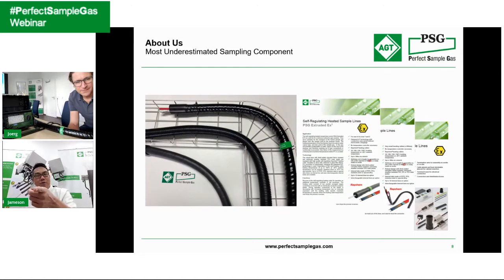The PowerPoint slides show three different bending radii for the heated line. The one on the extreme right, bending the most, will catch many people by surprise - how can a heated line bend up to 90 degrees on a cable tray? Usually the standard bending radius, shown at the bottom, is not appreciated by many people. They're not aware that these products really save a lot in terms of cost of ownership and performance.